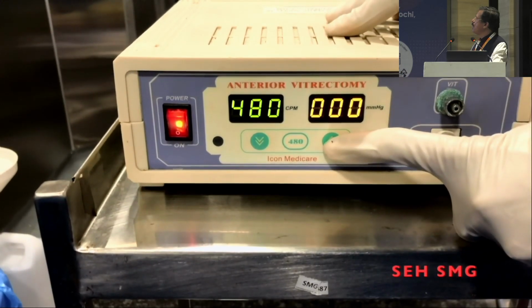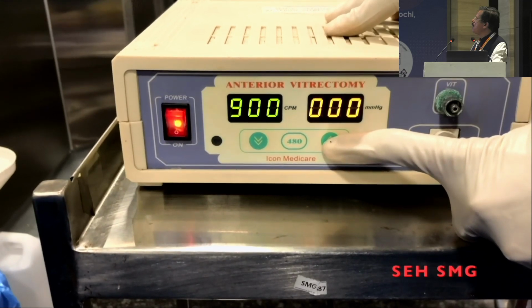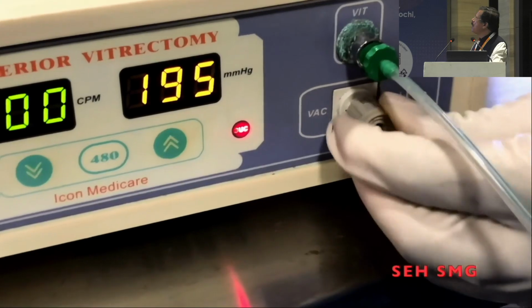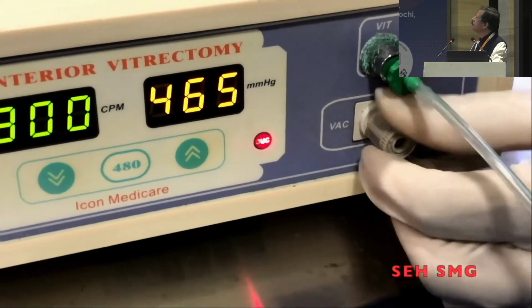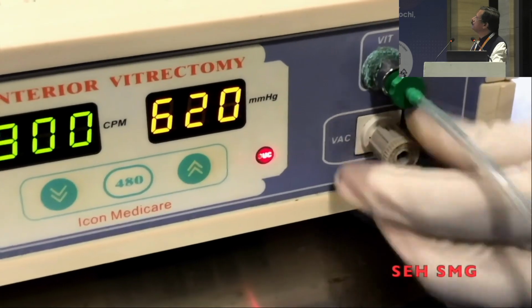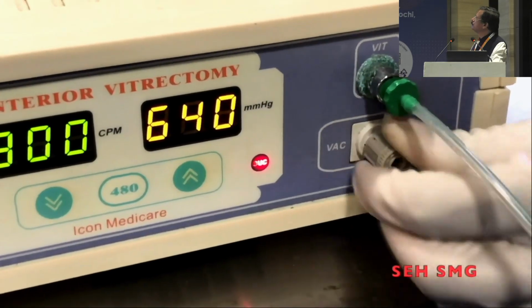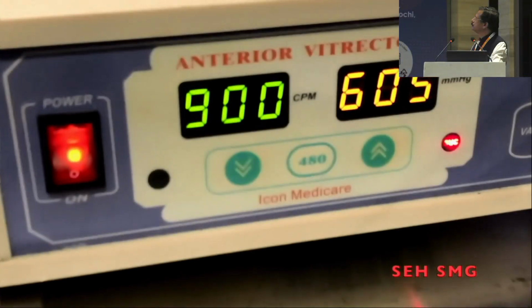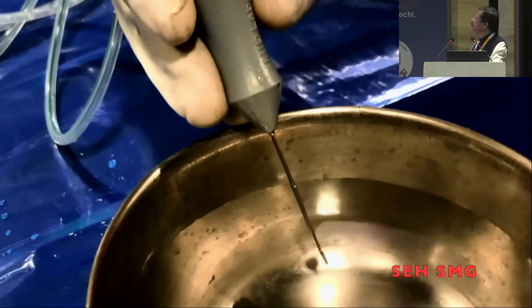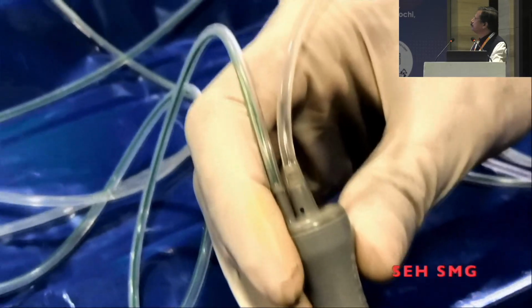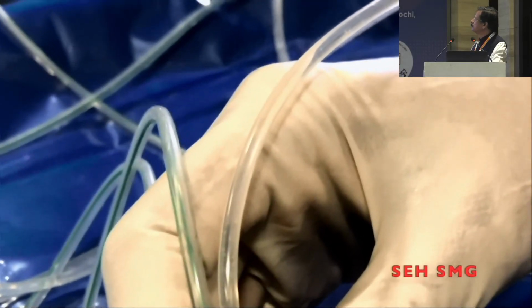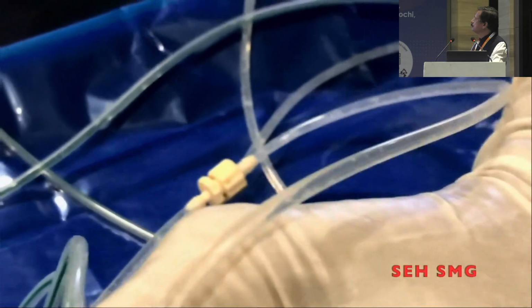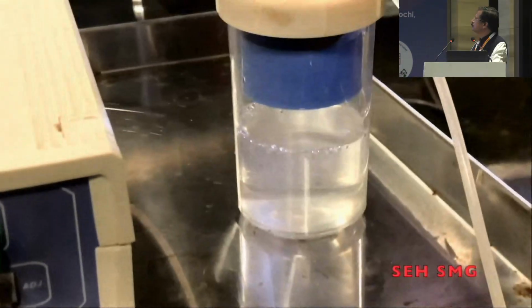Now we can adjust the cutting rate. It can go up to 900 cuts per minute. And we also can adjust the vacuum by pressing on the foot pedal and rotating the knob. In this machine, we can set up to 650 vacuum. To check the cutter, whether it is working or not, put it into a bowl containing BSS. First aspiration, press on the foot pedal. You can see the BSS getting aspirated and collected into the vacuum bottle.